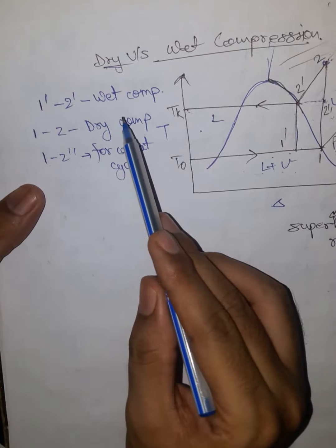Intermittent flow means that they do not supply the compressed substance continuously, while these are the continuous flow machines. Now there is a limitation in the compressors about handling of a particular substance that can be compressed in them. Now in case of reciprocating compressors, the wet compression process, or the compression in this liquid plus vapor region, is not found suitable. This is due to two reasons.